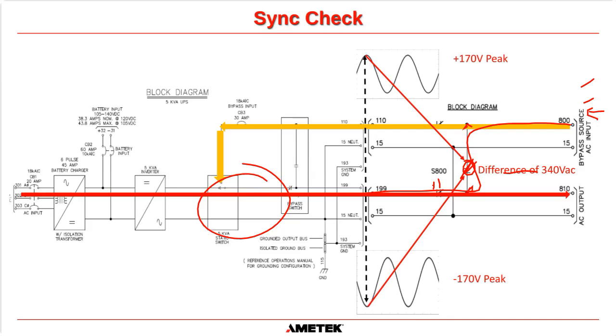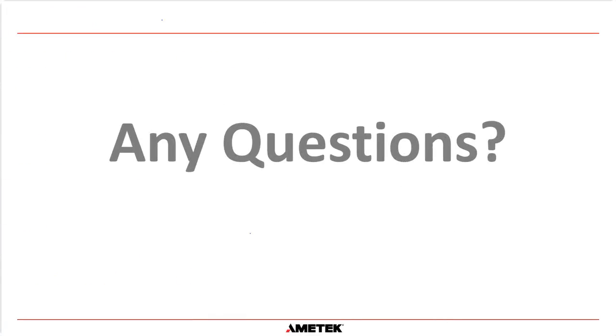And then obviously you've moved this switch to the bypass position, and if you don't have bypass available, then your load no longer has power. It will be a load drop. Okay, so that's why it is important to make sure the system is in sync, and that's the easy way to do it.